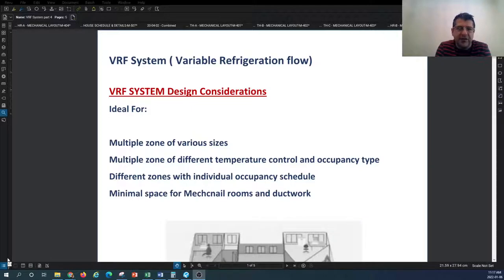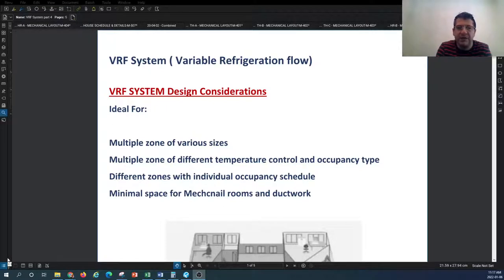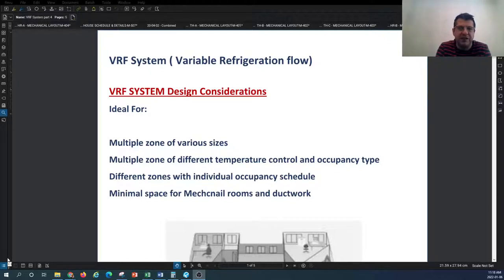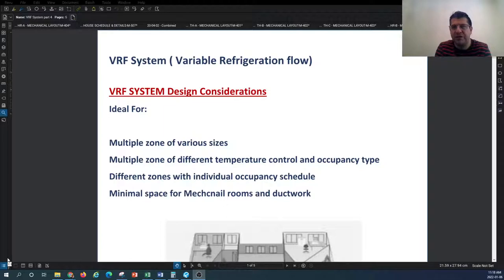As we touched on before, the VRF system is ideal for multiple zones with various sizes. We talked about facilities with different types of usage, different temperature control requirements, and different occupancy types. This is a good application because you can provide heating and cooling at the same time with different temperature control. Another important factor is that if you have individual occupancy schedules requiring independent control from other parts of the building, VRF provides good diversity in occupancy scheduling and independence of temperature control based on the dedicated zone.